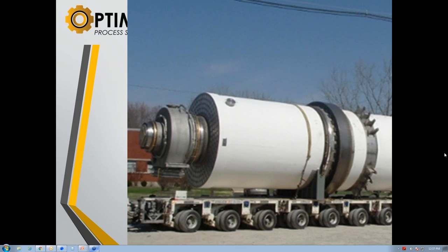And so you've changed the shape of that tube and flattened it out and imparted it into that tube sheet. If requested, we'll be glad to roll it, and then we would weld it to the tube sheet, and then we'd re-roll it. That just makes for a really good seal. Years down the road, when you go to change it out, it makes it a little bit more complex to get the tube out and change tubes.